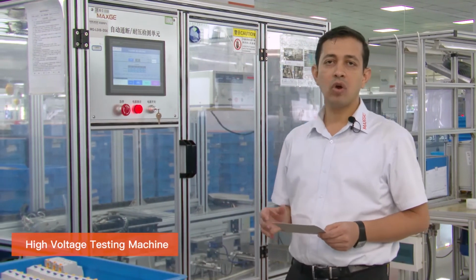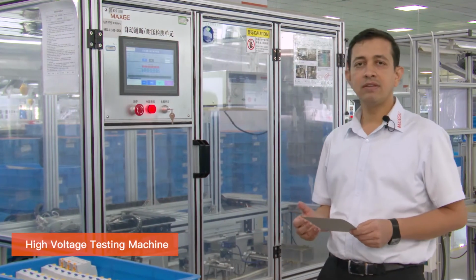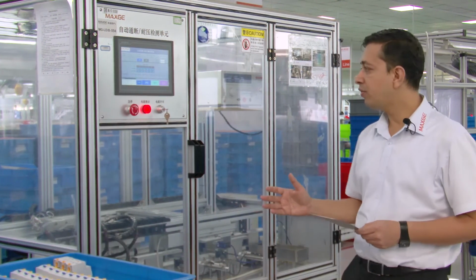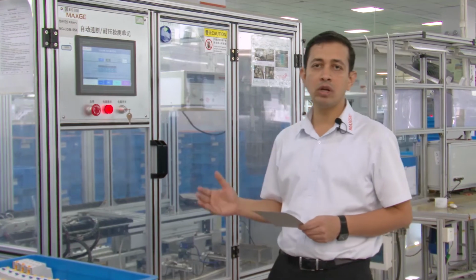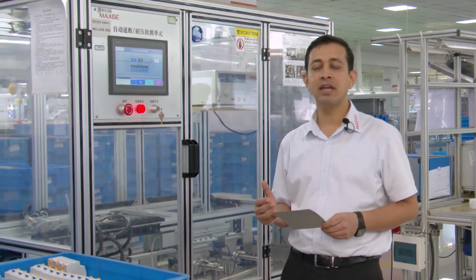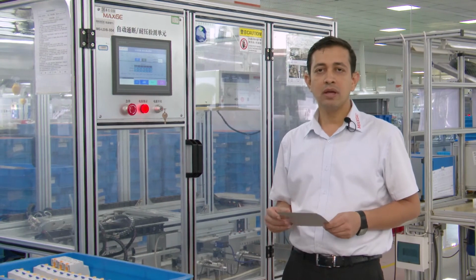Now we are at the high voltage testing station. After all the calibrations have been finished, this is the last stage of the testing, where we apply 2.1 kilovolt for 1 second, and we see whether the RCCB has any leakage current passing through or not. The leakage current should not exceed 20 milliamperes.